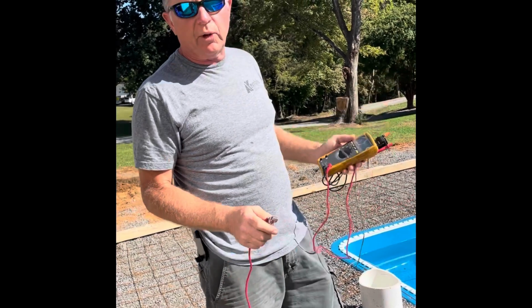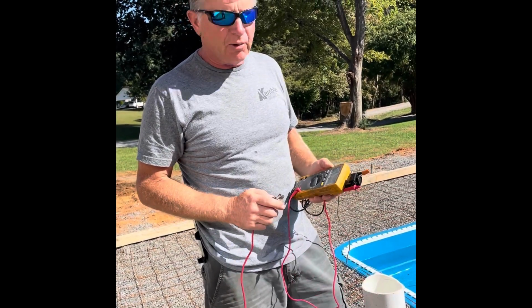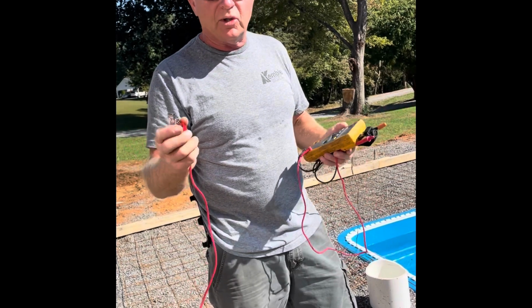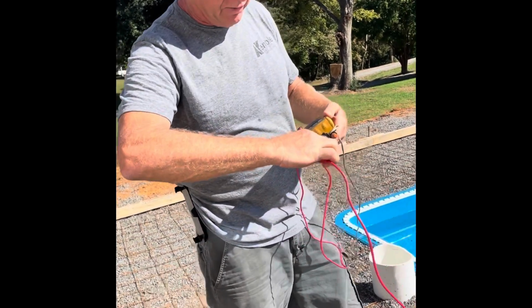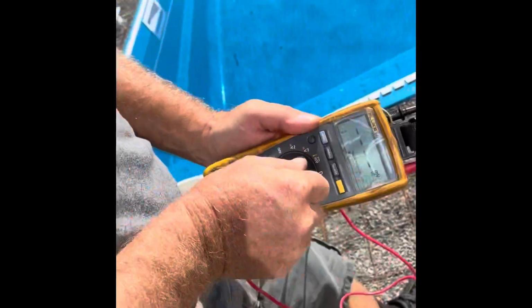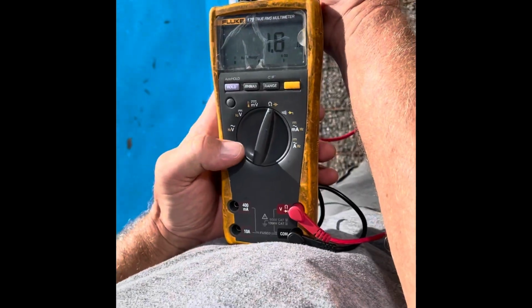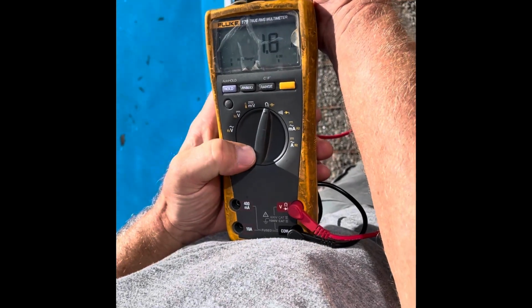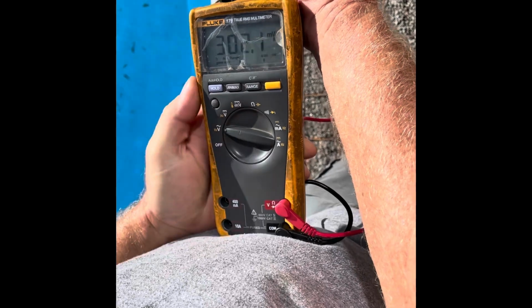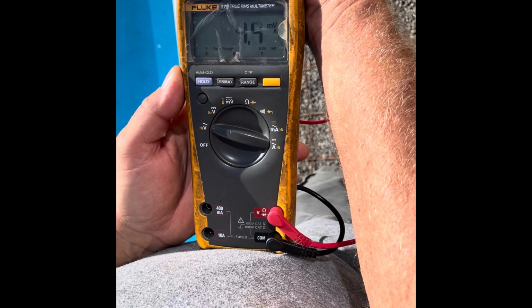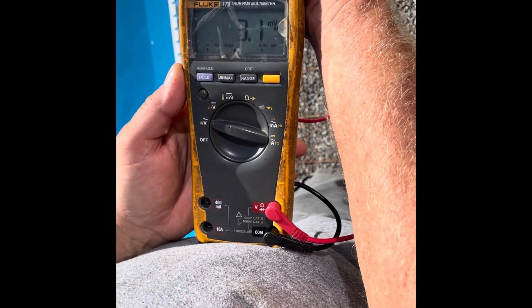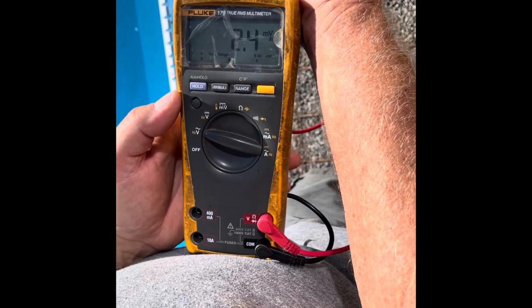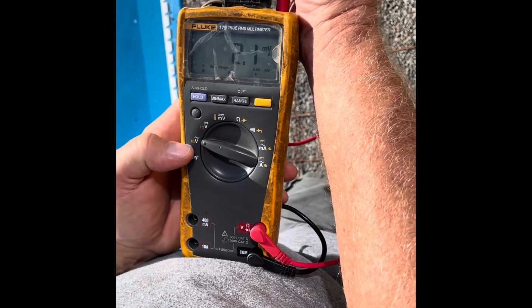So the next thing we're going to check is to be sure that the voltage potential from any one point on the grid to another point is at 0. The first thing I would caution you to do is just check your lead and see what the voltage might be, because like I said earlier, when we checked our continuity, we see the length of our wire comes out at 1.8, and then if we switch it over to voltage, we're going to see just a little bit of voltage present. We're going to see that same thing when we connect to the grid. Just so you know, you're not going to be reading at 0. However, when we switch to DC, you're going to see it goes directly to 0.